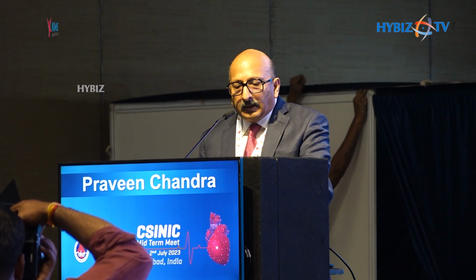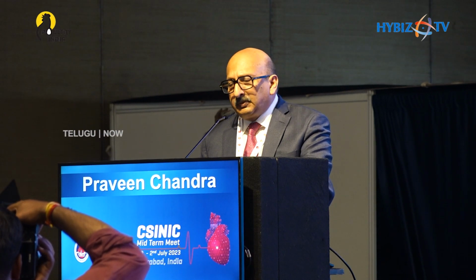So this is the catheter which we use, which uses the light spectrum. And when we do this, there are certain issues which we have to keep in mind: we have to keep flushing while we are doing the laser, advancing at a slow speed, and controlling the fluence. Fluence means energy, and the pulses means the speed. So that we control. There's the console, which I'll show you, and this console controls that. And the vessel to catheter ratio. Generally, the 0.9 catheter is good for most of these patients. So typically, 90% of the time you will be using a 0.9 catheter. There are 1.4, 1.7, 1.9, but 0.9 is very safe, very good.